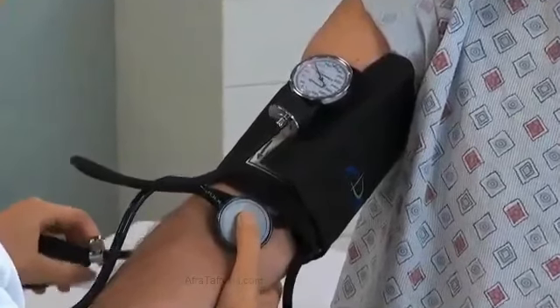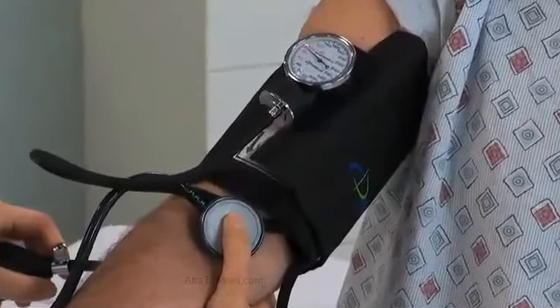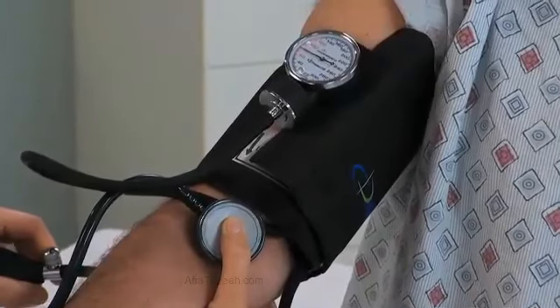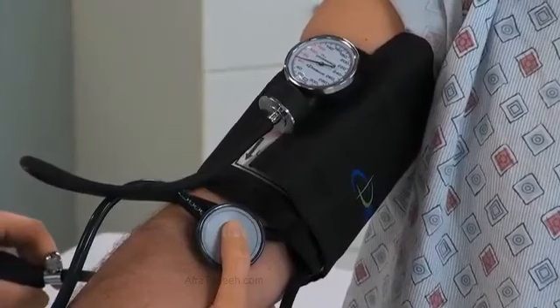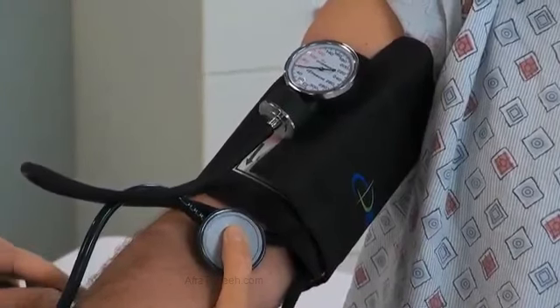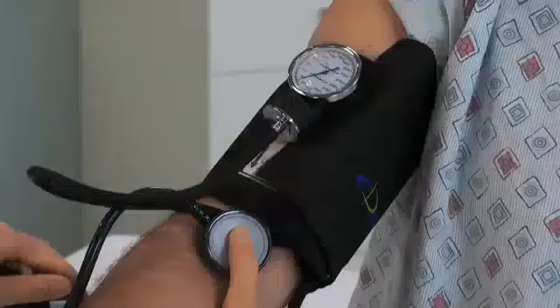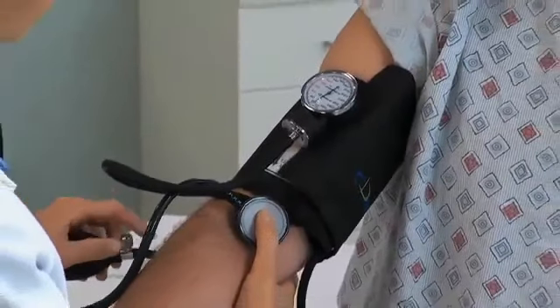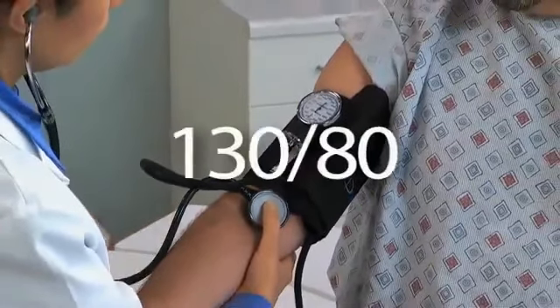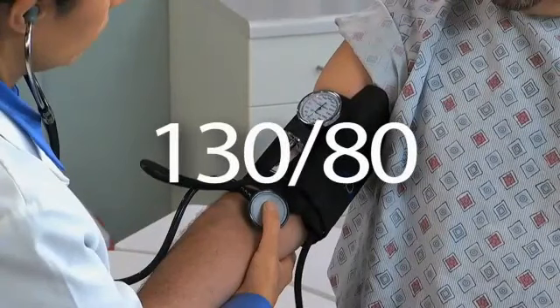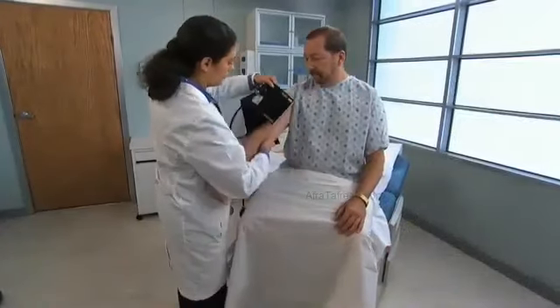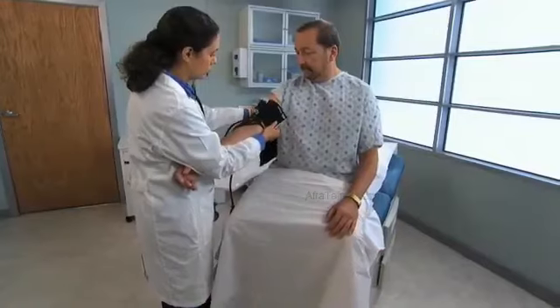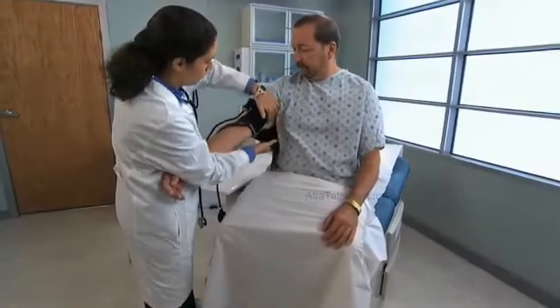Continue to lower the pressure slowly until the sounds become muffled and then disappear. To confirm the disappearance of sounds, listen as the pressure falls another 10 to 20 millimeters. The disappearance point, usually only a few millimeters of mercury below the muffling point, provides the best estimate of true diastolic pressure in adults. Read both the systolic and the diastolic levels to the nearest 2 millimeters of mercury. Wait 2 or more minutes and repeat the entire sequence. Average your readings. If the first 2 readings differ by more than 5 millimeters of mercury, take additional readings.